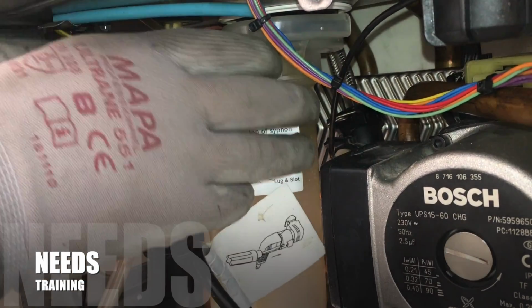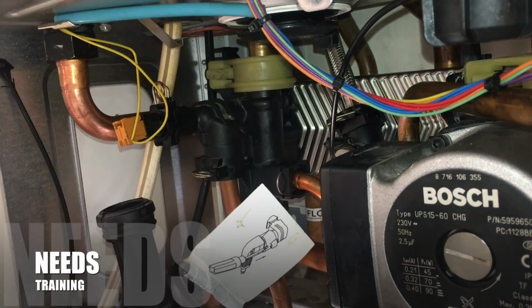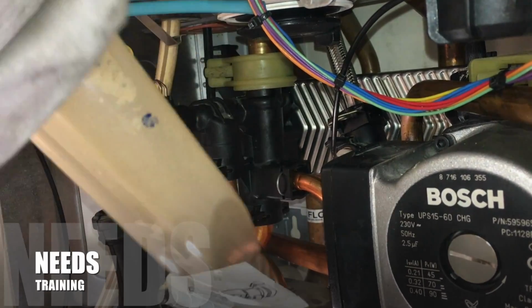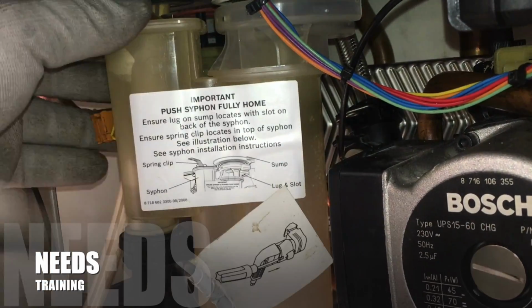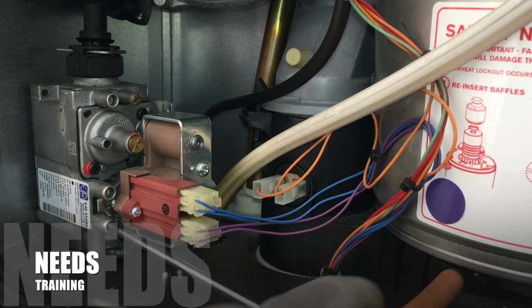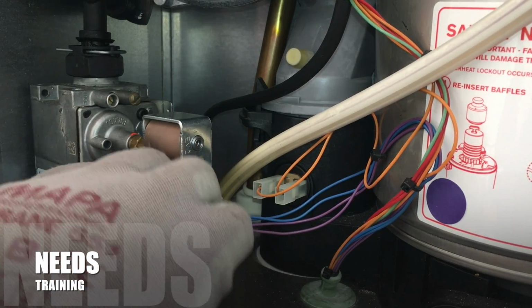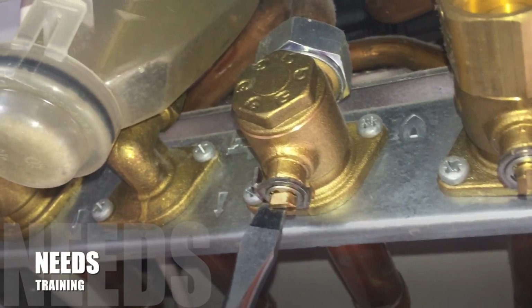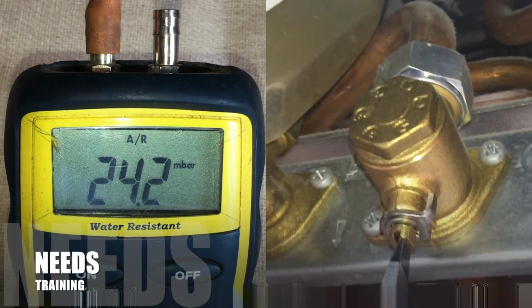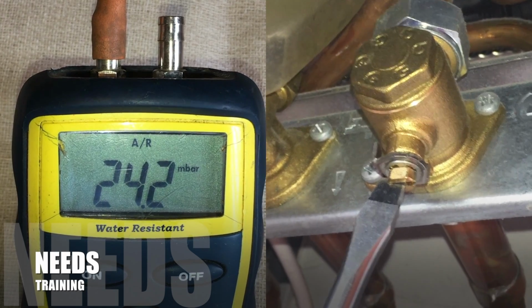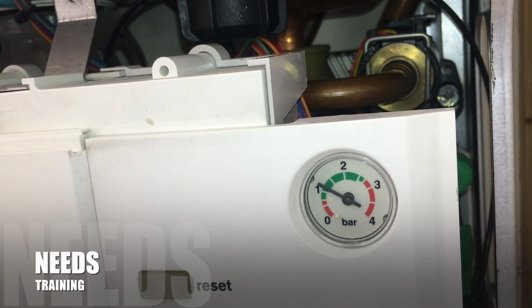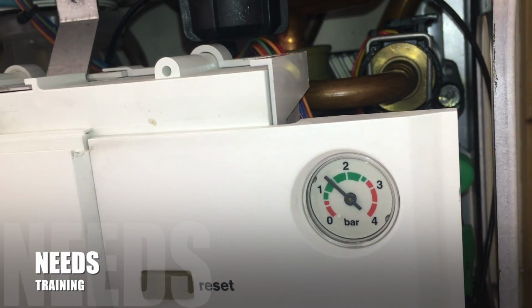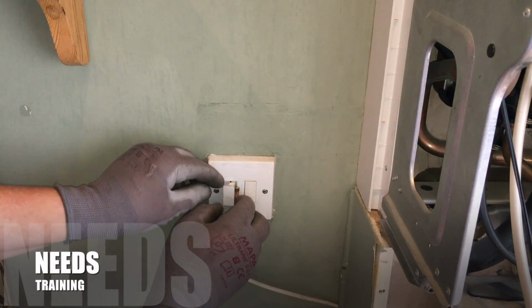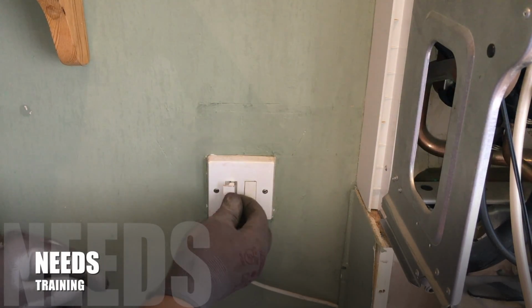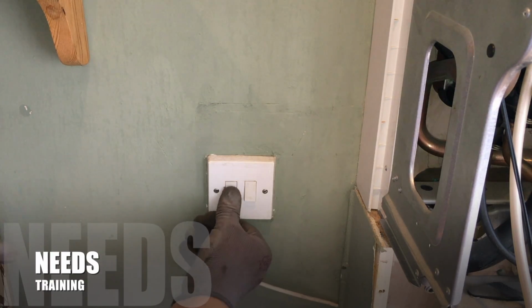Remove and clean the condensate siphon. Now check the gas valve for letting by. You can now repressurize the appliance to 1.5 bar. Put the 3-amp fuse back into the spur and turn the power back on.